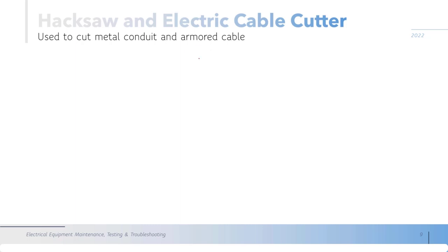An armored cable is a cable with protection, the type of cable you use in ground installations. So armored refers to a specific metal that will protect the installation of the cable. Because when the cable is in the streets, you cannot control all the cables in the ground installation. So let's suppose someone is working and decides to open a hole in the ground in front of his house. With the tool he cuts the cable. So if the cable is not armored, he will get electrocuted and will damage the cable. But when the cable is armored, the tool he is using to open the hole will not damage the cable.